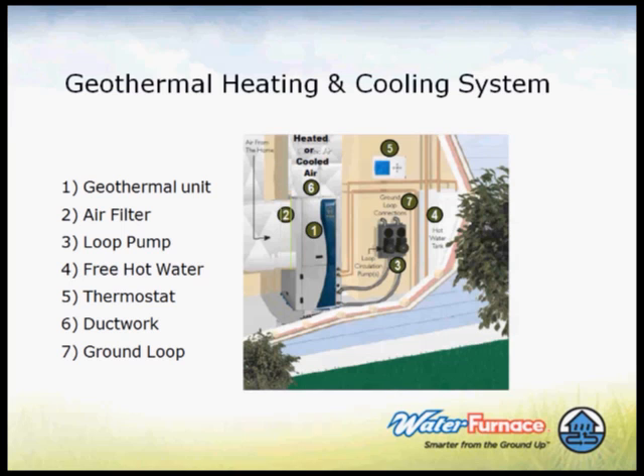Which is more efficient, water to air or water to water? It depends. On paper, the water to air performance numbers are higher, but it's not really a fair comparison because there are so many other benefits to water to water, like a radiant floor. If you have a 30-foot entryway or a 15-foot entryway, you only have to heat head high, and when you walk in and your feet hit that warm floor, your body feels really good. There's been a rash of this for horse barns, where people want to keep the horses somewhat warm without heating all the height and everything. That doesn't really factor into the efficiency comparison. It's a tough question, but on paper water to air is more efficient, though there are a lot of mitigating circumstances.